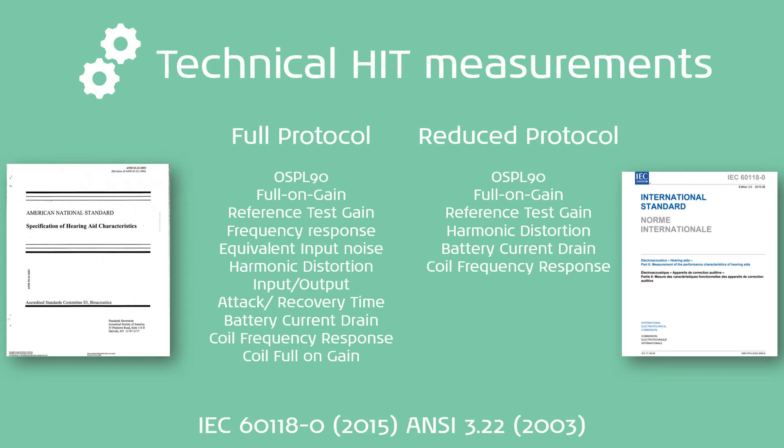For both sets of standards, you can run either a full protocol or a reduced protocol. Reduced protocols are more commonly used in the clinical setting, where a full protocol may be used if there is a particular concern about particular features or factors of the hearing aids themselves.